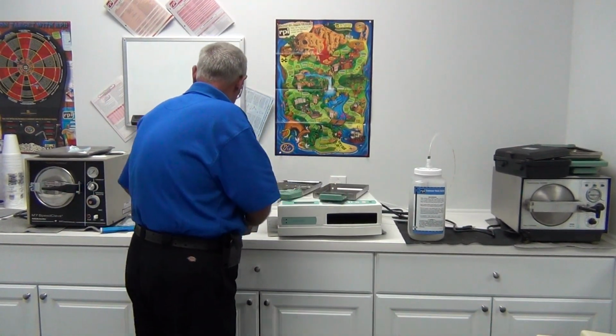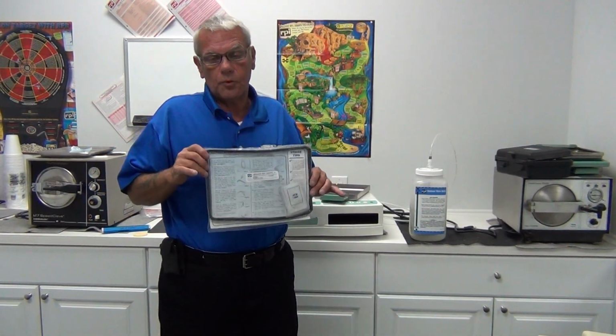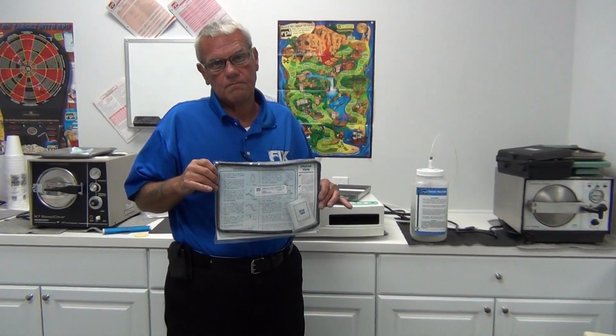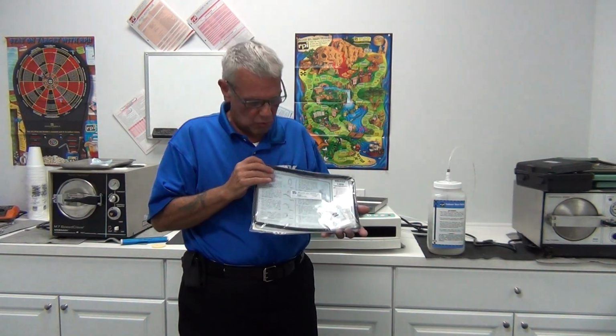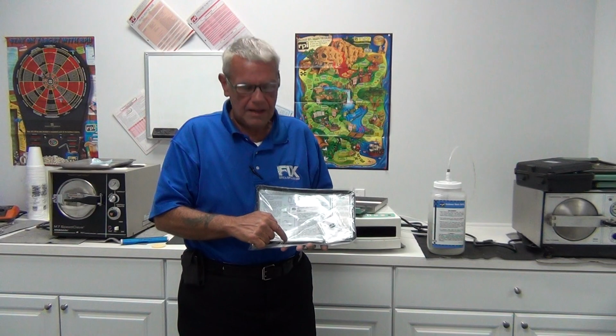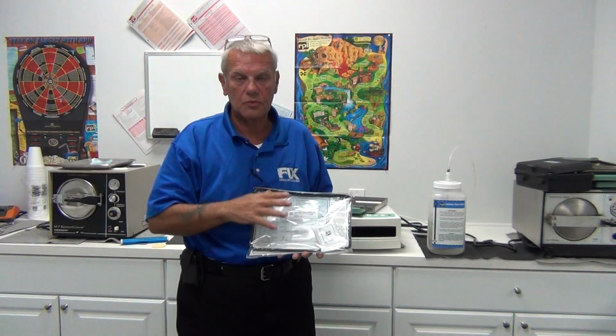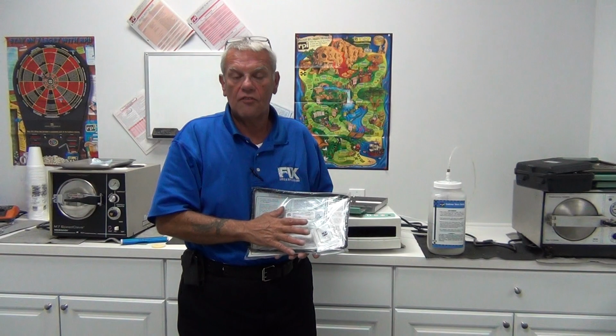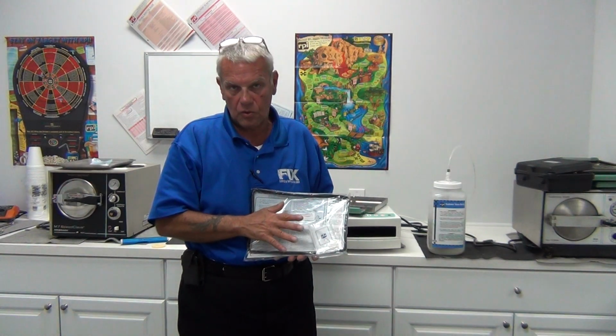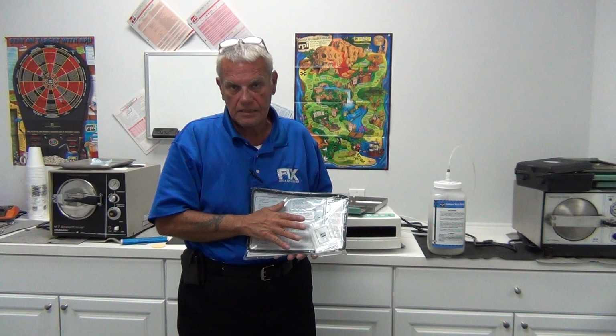If we do need to change a cassette gasket, the cassette gaskets are only good for approximately 800 cycles. That's not a lot of cycles. Statim recommends 800 cycles, RPI recommends 800 cycles. This is the gasket as it will come with some lubricating soap. I'm not going to go into replacing the gasket. We've already replaced the gasket before. The gasket has step-by-step instructions on a handout that comes with every new gasket. Never, ever, ever reuse an old gasket. You're asking for trouble. Never reuse one.